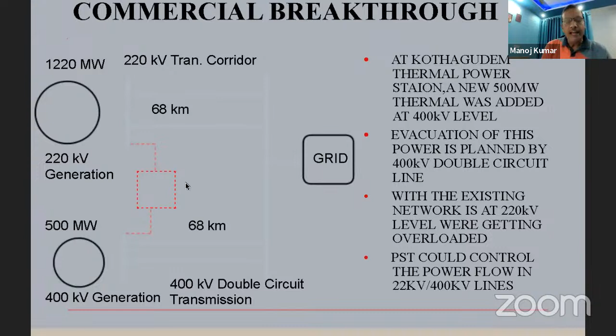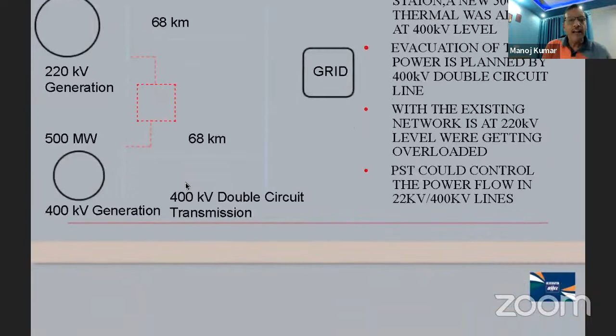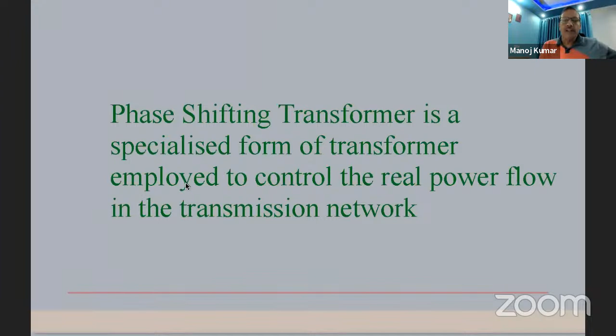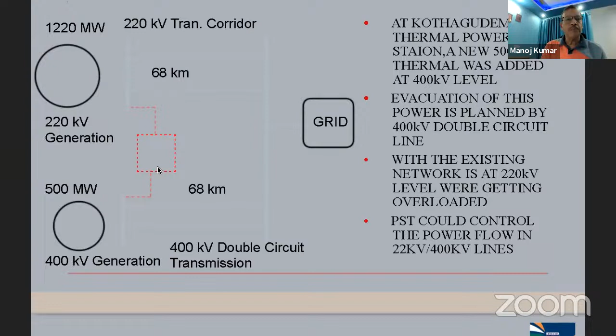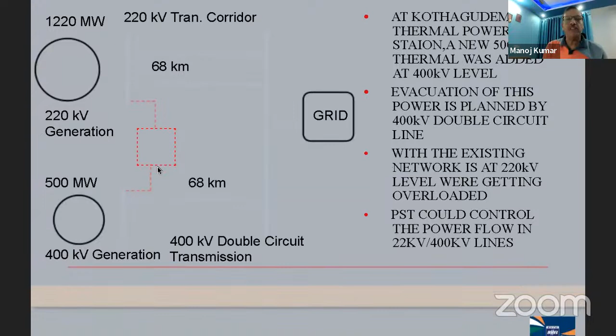So based on the system studies, BHEL designed a phase shifting transformer for the first time in India. That was a 400 kV unit, which has already been installed at Kothagudem and is working satisfactorily as on date. This transformer basically controls the power flow between the 220 kV line and the 400 kV bus as per my desired requirement. I will touch upon the principle of how, even though it is a passive element, the power transfer is controlled.